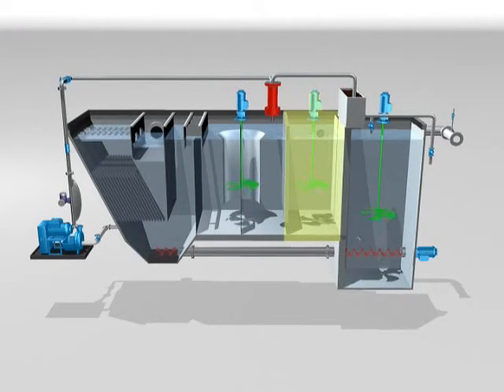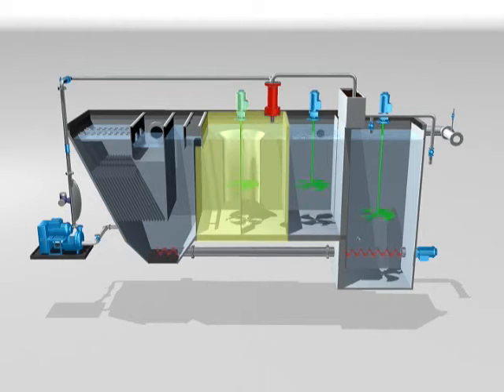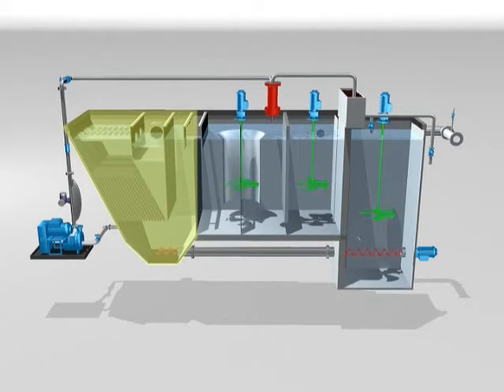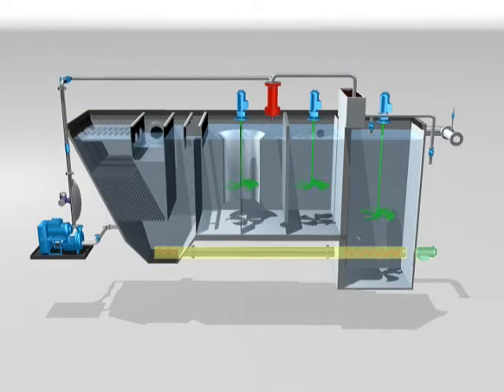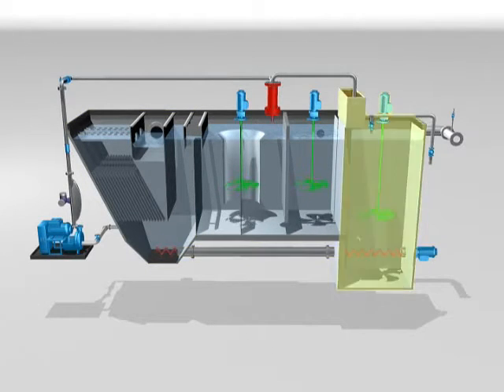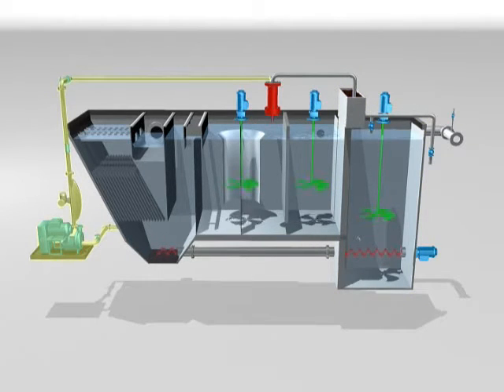Active Flow Turbo consists of a coagulation basin and a flocculation basin with a turbomix reactor, followed by a lamella settler and a sludge thickening tank. An endless screw transports the microsand sludge slurry from the settler to the thickening tank, which includes a mixer and a centrifugal pump for pumping the sludge slurry to a hydrocyclone for microsand cleaning and recovery.